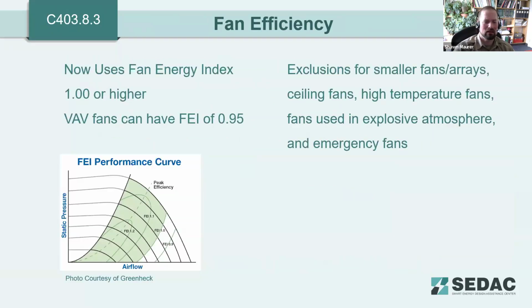Another significant update as far as fan efficiency for buildings, the fan energy index is now being used instead of the fan efficiency index. What was noted in the past was that for varying performance levels, you would have the same fan efficiency index. The fan energy index better accounts for the entire system, including VFD, banks of fans, and how they perform. It accounts for changes in shaft power, VFD, and so on in that value. So we're now using that fan energy index instead of the old efficiency index.